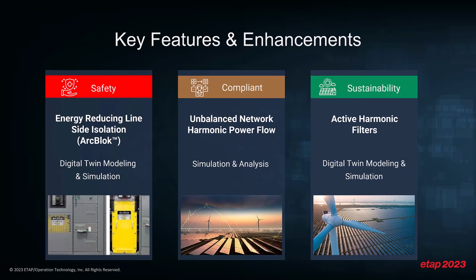ETAP is continuing its mission to also bring compliance assessment tools by addressing an emerging industry problem driven by the proliferation of renewables, electric vehicles, and other technologies in the power distribution systems. Unbalanced networks and the ever-increasing presence of harmonics in the power network are also driving the need for more efficiency, minimization of unbalanced conditions, and therefore minimization of losses to improve the sustainability of power networks. Active harmonic filters are able to compensate for unbalanced condition and active harmonic cancellation in such situations. ETAP 2023 now includes detailed modeling of active harmonic filters, including vendor-specific models, taking the guesswork out of placement, sizing, and the effectiveness of these devices when distributed throughout the network.